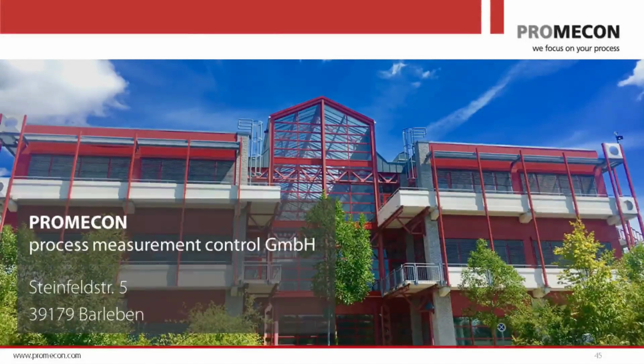Because it means that the same amount of heat will remove the same amount of moisture from the same coal. And if that's not the case, well, physics is the same in all the mills. So where's the flaw? And usually it's a flow measurement that's not working correctly, and most of the time it's an airflow measurement that's causing you the problem.